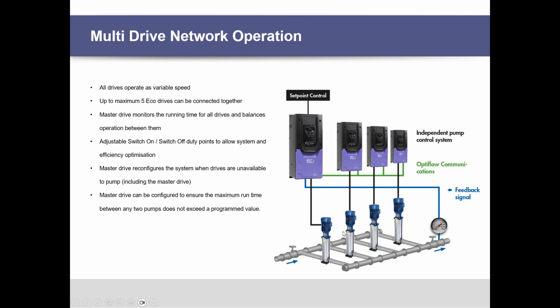So we can also rotate the run times on these pumps to keep the run time as close together as possible, so that if you go to site to do maintenance, you can set the drives so that they never have a runtime difference greater than 24 hours. So it makes it really nice and simple. You can go in and do maintenance on all of the drives, all of the motors, all of the pumps in one visit, rather than having to go back and forth.